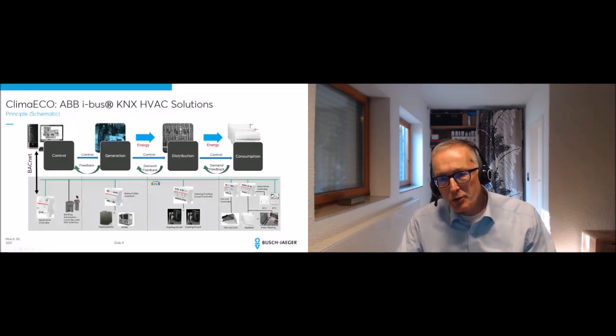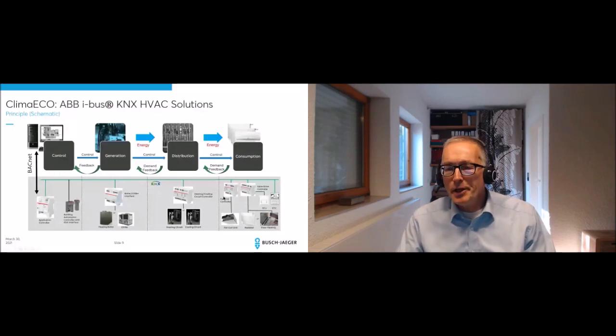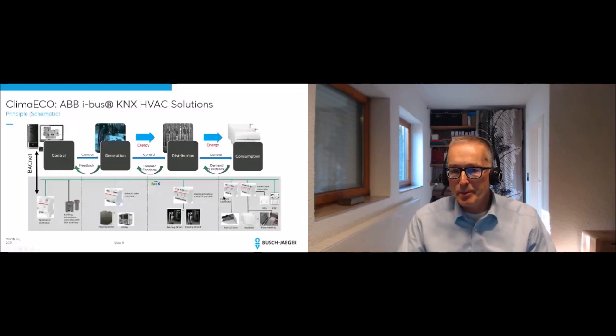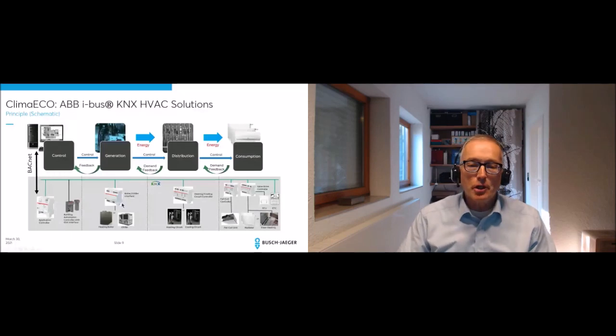And on the right side, we call it consumption. There we have our typical room-oriented devices, so fan coil controller, split unit gateway, valve drive controller, and of course also the operating elements, room temperature controller to do the job in the room. We did that already before, but now we can also touch the distribution part with the heating cooling circuit controller and the boiler chiller interface, the generation of hot and cold water together with the boiler chiller interface.